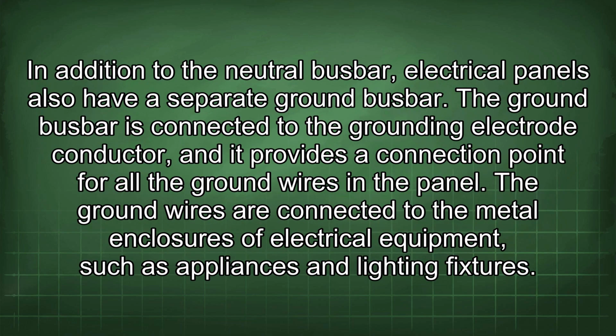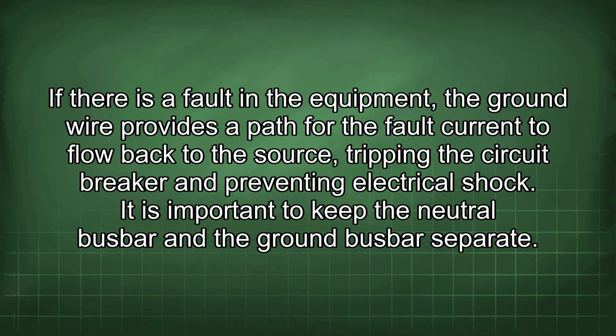In addition to the neutral busbar, electrical panels also have a separate ground busbar. The ground busbar is connected to the grounding electrode conductor, and it provides a connection point for all the ground wires in the panel. The ground wires are connected to the metal enclosures of electrical equipment, such as appliances and lighting fixtures. If there is a fault in the equipment, the ground wire provides a path for the fault current to flow back to the source, tripping the circuit breaker and preventing electrical shock.